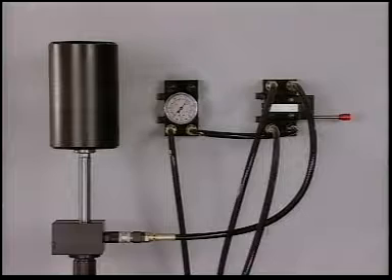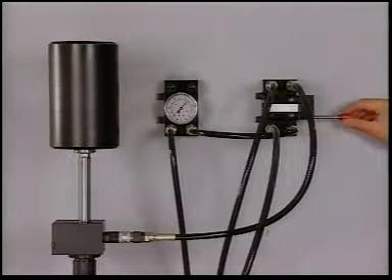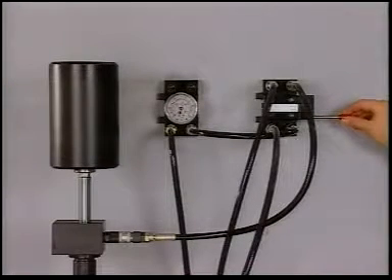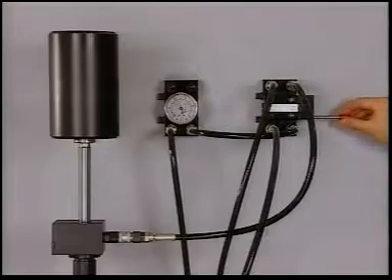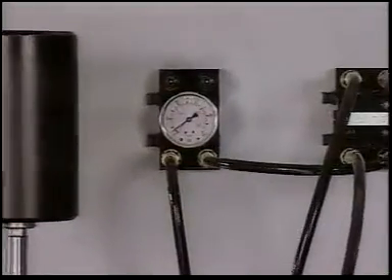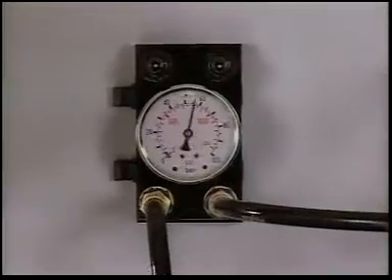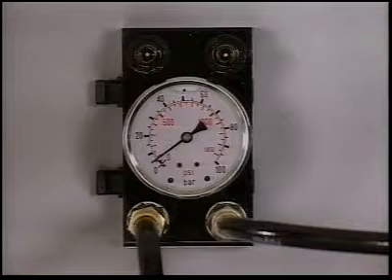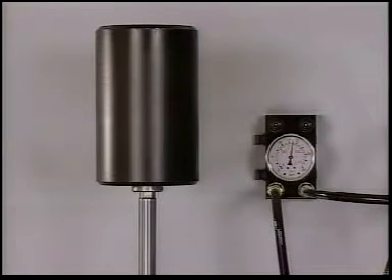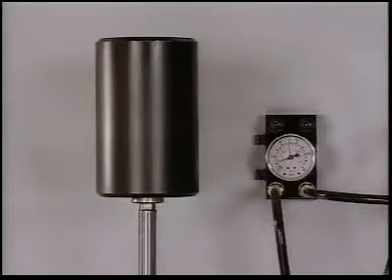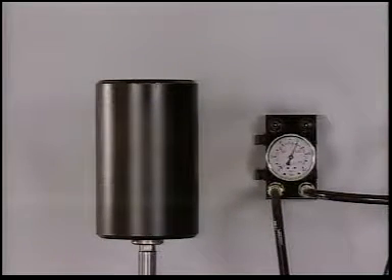This experiment illustrates another characteristic of directional control valves: switching overlap. This characteristic determines how a valve will behave during switching. Here we have a valve with positive switching overlap, which means that during the transition from one switching position to the other, the ports remain blocked and are not opened until the end position has been reached. This has the effect of maintaining system pressure during the switching process, so that a drive under load does not momentarily sink.